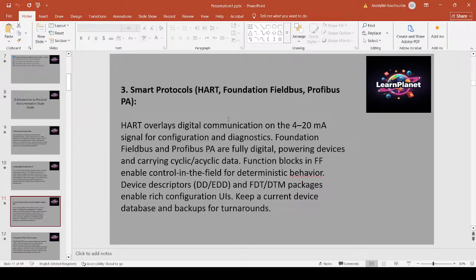Smart protocols: HART, Foundation Fieldbus, Profibus PA. HART overlays digital communication on the 4-20 milliamp signal for configuration and diagnostics. Foundation Fieldbus and Profibus PA are fully digital, powering devices and carrying cyclic data. Function blocks in FF enable control in the field for deterministic behavior. Device descriptors DD, EDD, and FDT/DTM packages enable rich configuration UIs. Keep a current device database and backups for turnarounds.